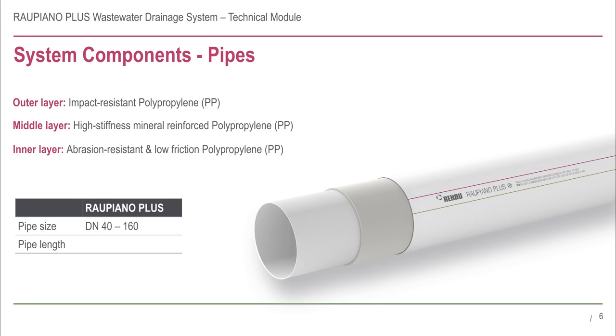RAUPIANO Plus pipes are technologically advanced and are comprised of three distinct layers. The outer layer is made from an impact resistant polypropylene material. The middle layer is a high density mineral reinforced polypropylene layer that reduces vibrations caused by sound energy. The smooth inner layer is made from abrasion resistant polypropylene, and its low coefficient of friction makes it difficult for particles in the wastewater to adhere to it.